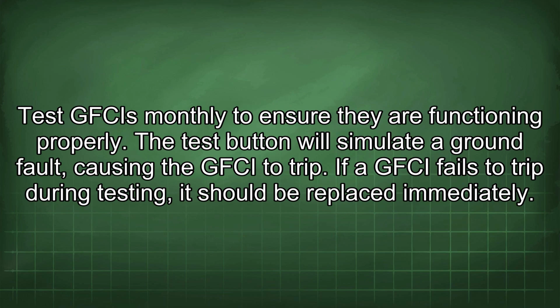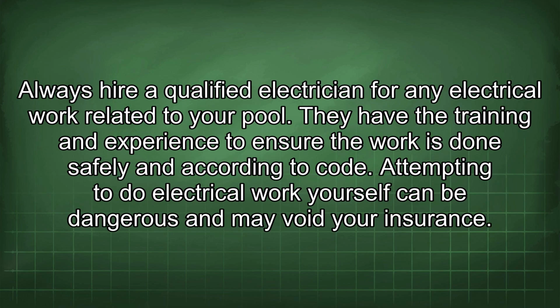Test GFCIs monthly to ensure they are functioning properly. The test button will simulate a ground fault, causing the GFCI to trip. If a GFCI fails to trip during testing, it should be replaced immediately. Always hire a qualified electrician for any electrical work related to your pool. They have the training and experience to ensure the work is done safely and according to code. Attempting to do electrical work yourself can be dangerous and may void your insurance.